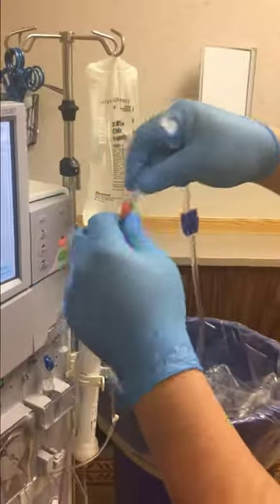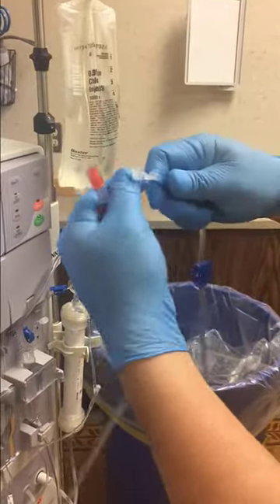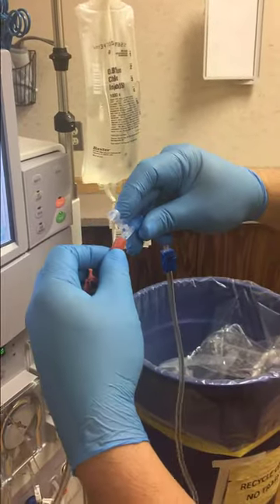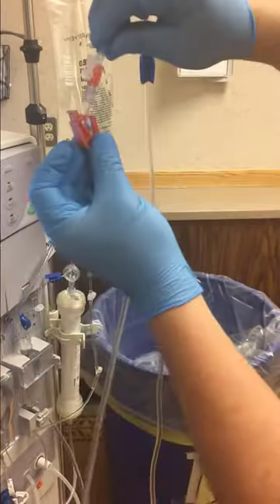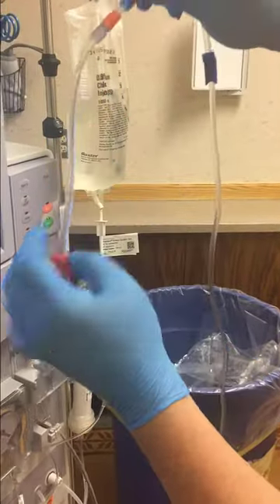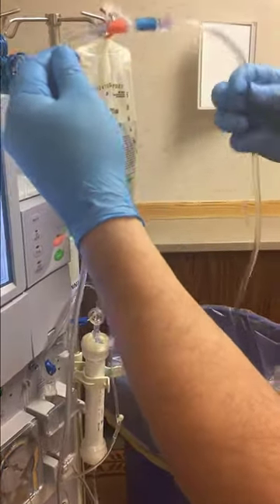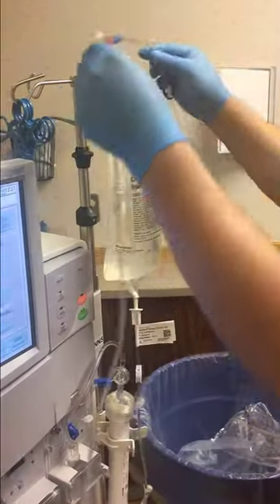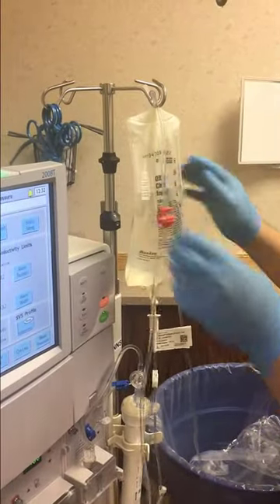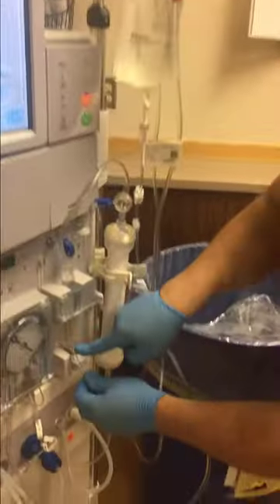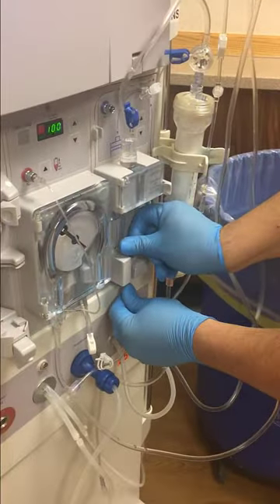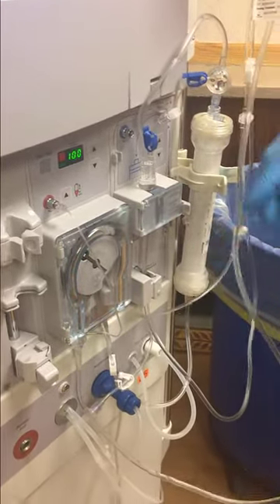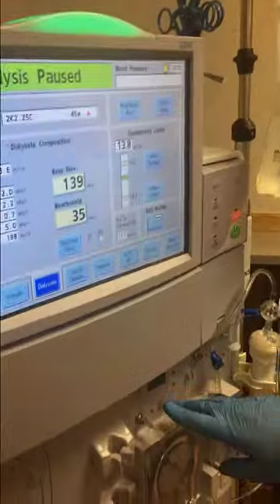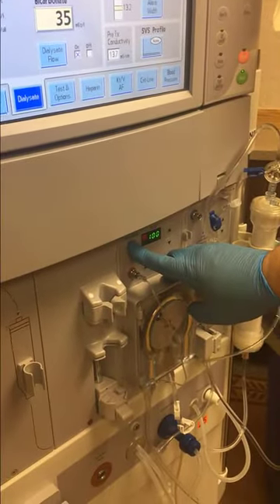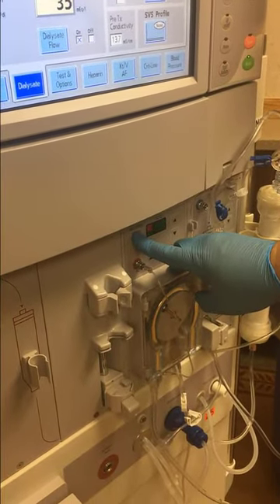Then the lines have to be married together. So take one of the ends, the protective ends, off and throw it away. Open the other end and firmly put the two pieces together and open your clamps so that saline can freely circulate. Now thread the venous clamp. And now we're ready to go into the machine and place the machine into test.